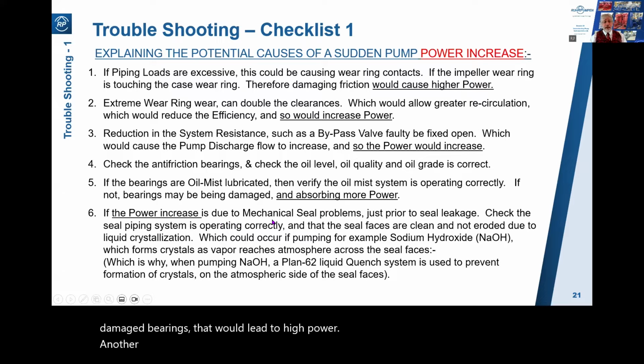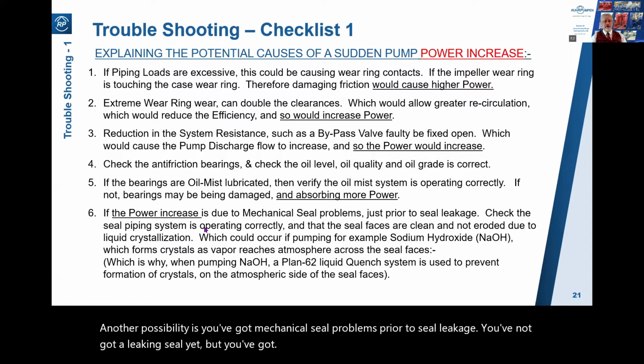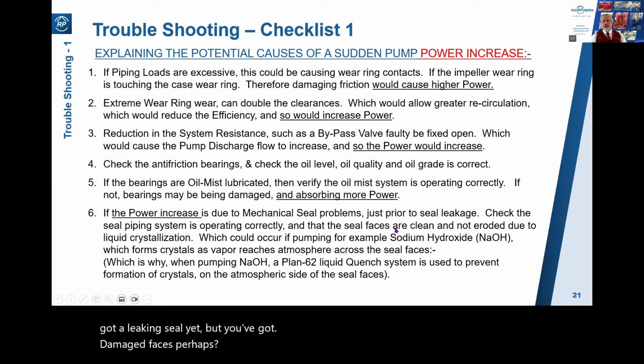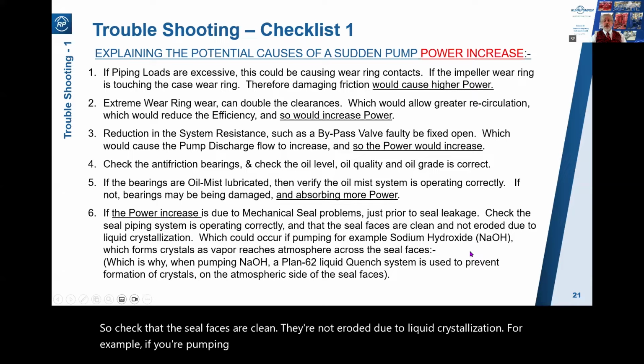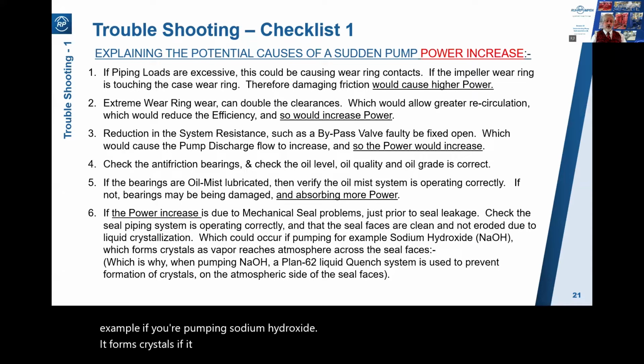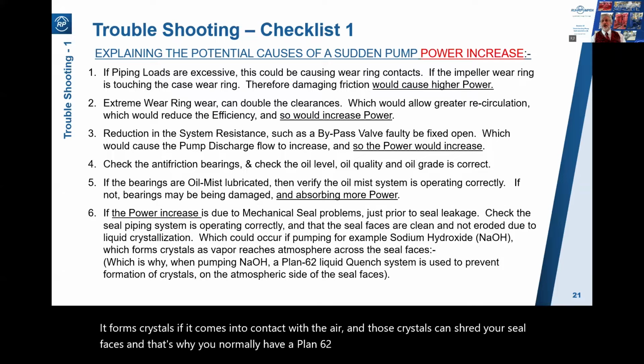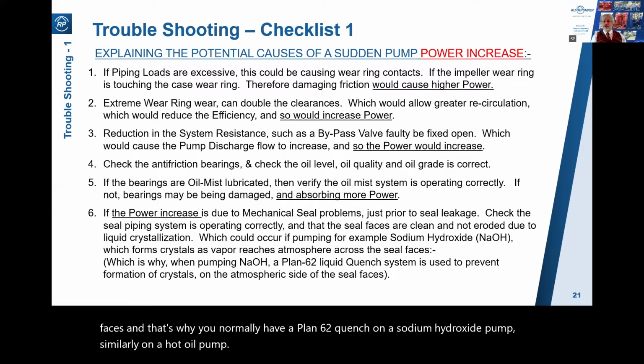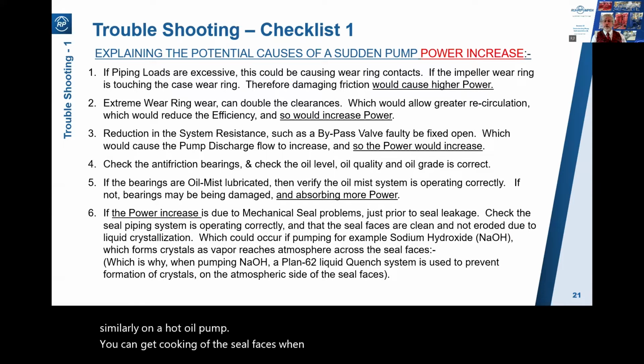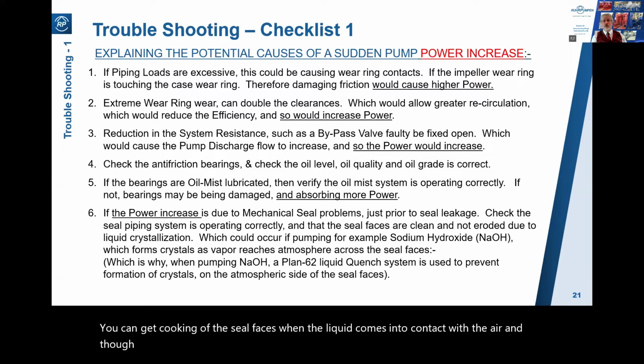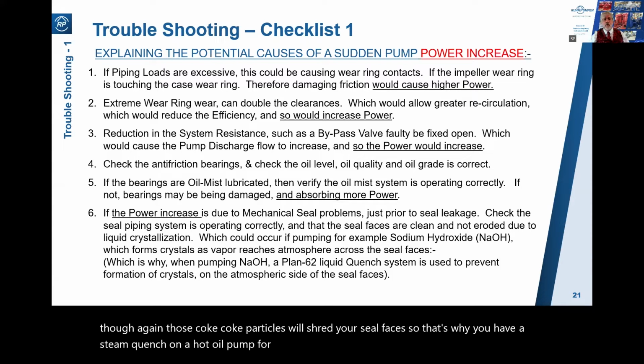Another possibility is you've got mechanical seal problems. Prior to seal leakage, you've not got a leaking seal yet, but you've got damaged faces, perhaps. So check that the seal faces are clean and not eroded due to liquid crystallization. For example, if you're pumping sodium hydroxide, it forms crystals if it comes into contact with the air, and those crystals can shred your seal faces. And that's why you normally have a Plan 62 quench on a sodium hydroxide pump. Similarly, on a hot oil pump, you can get coking of the seal faces when the liquid comes into contact with the air, and those coke particles will again shred your seal faces. So that's why you have a steam quench on a hot oil pump, for example. So those are obvious things to check.